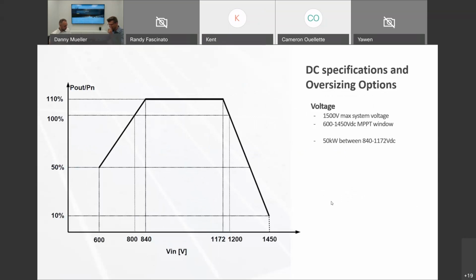Jumping right into the DC specifications, the inverter is designed as a multi-MPPT inverter. So in the old days, you had a big inverter, it only had one input, and you had a combiner box in the field where you combine all these strings, however many, 10, 12, or even more strings in parallel. Modern designs typically go away from that concept and eliminate the combiner box and switch to a concept where you have only two strings in parallel, and these two strings in parallel will then connect to a dedicated MPP tracker in the inverter. With the 45 KTL and the smaller 1000 volt units, you have 4 of those MPP trackers available, which also means that you have a more granular MPP tracking available to your system.